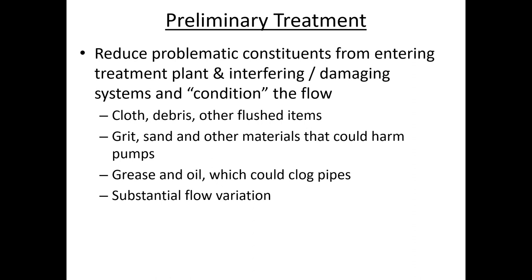There's also the case of tiny particulate material that's abrasive. Things like crushed glass or grit or sand. And those abrasive materials, if over the course of many years are not removed, could wear down pumps especially. And then, of course, things like grease and oil, when they cool, they increase their viscosity, they settle to the bottom of pipes, and they clog the pipes and reduce the capacity. So there's a real incentive to keep that out.